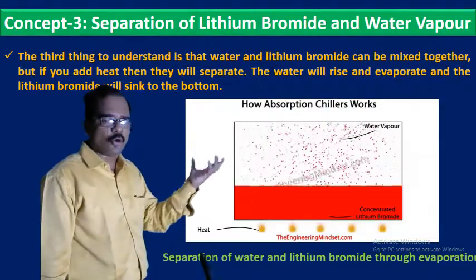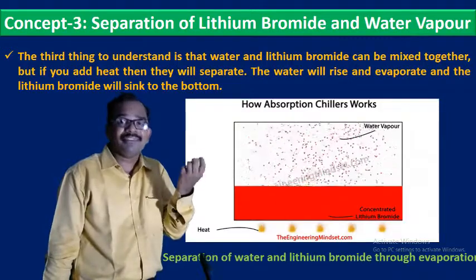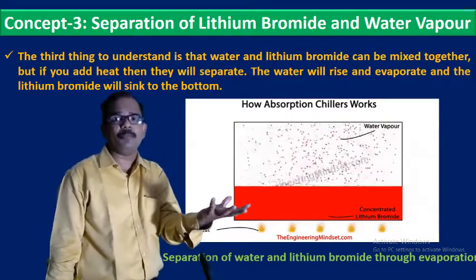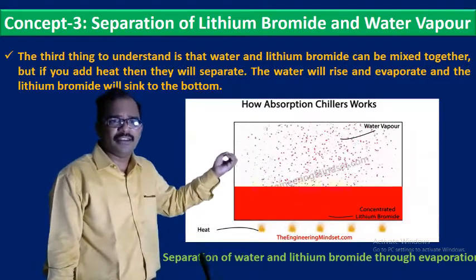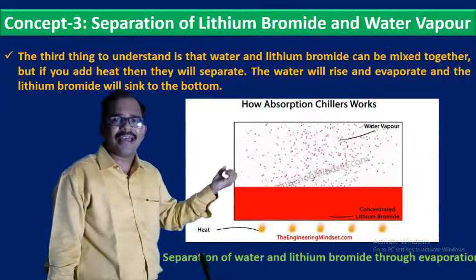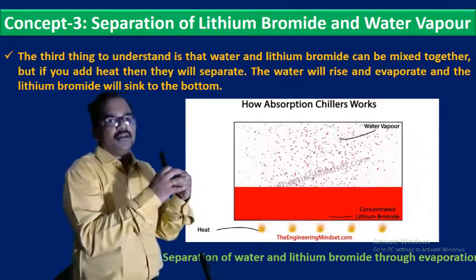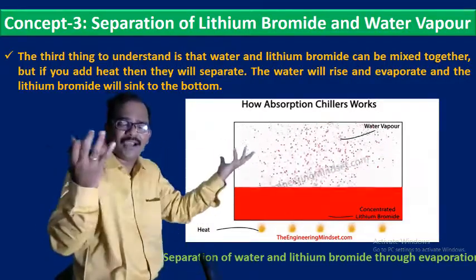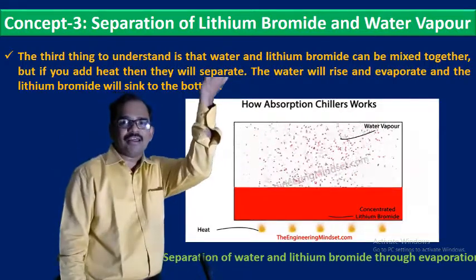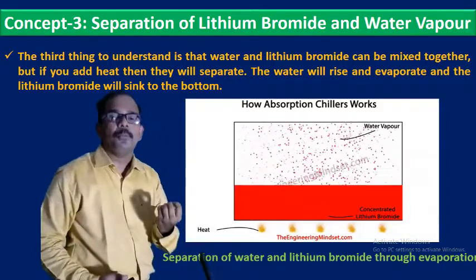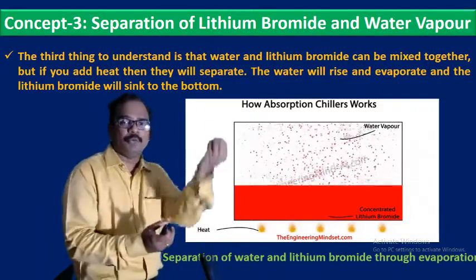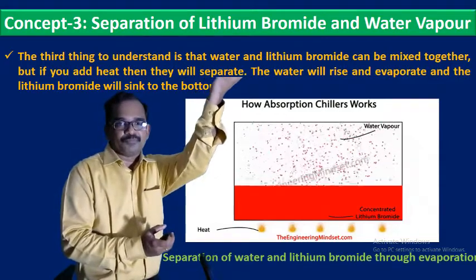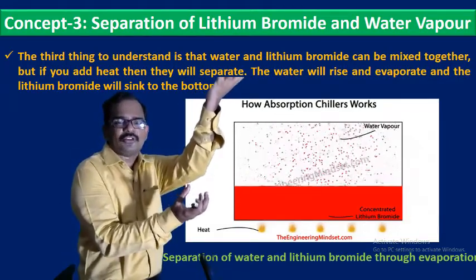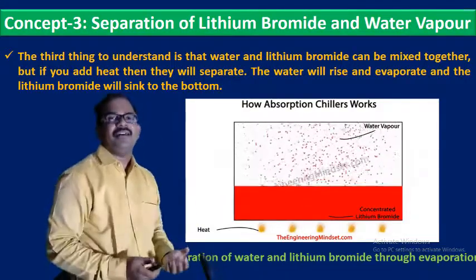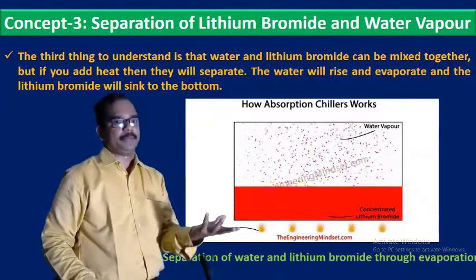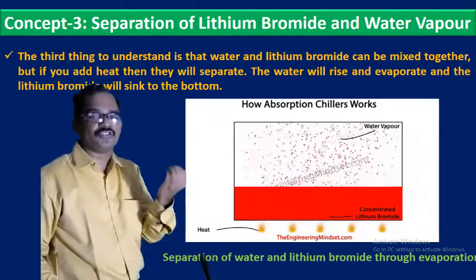The third concept is: after they got mixed with each other, how can we separate those two? There's a separation of lithium bromide and water vapor. The third thing we need to understand is that water and lithium bromide can be mixed together, but if you add some amount of heat, then both will separate. The water will rise and evaporate, and the lithium bromide will sink to the bottom of the container, because water has very low density and will move upwards by becoming vapor. Whatever is the leftover lithium bromide, because of its heavy nature, will sink to the bottom of the tank or the container in which it was kept. It is the third concept we need to understand.